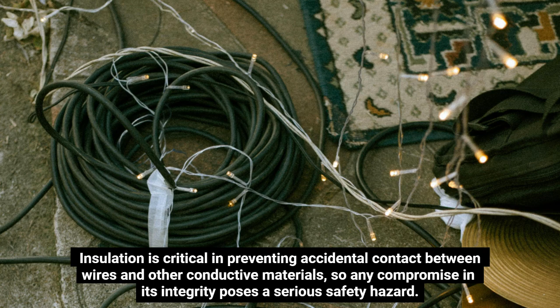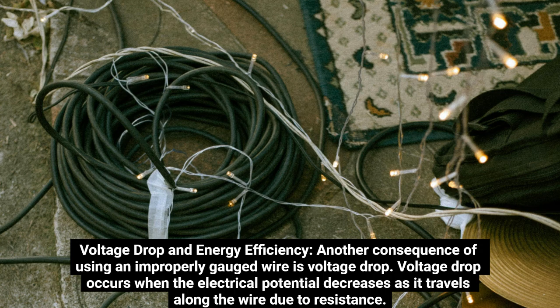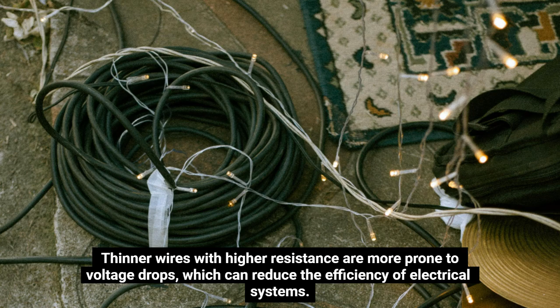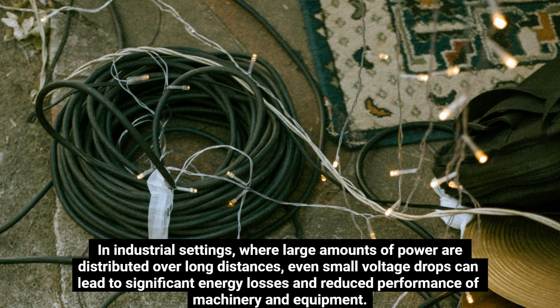Voltage drop and energy efficiency. Another consequence of using an improperly gauged wire is voltage drop. Voltage drop occurs when the electrical potential decreases as it travels along the wire due to resistance. Thinner wires with higher resistance are more prone to voltage drops, which can reduce the efficiency of electrical systems. In industrial settings, where large amounts of power are distributed over long distances, even small voltage drops can lead to significant energy losses and reduced performance of machinery and equipment.